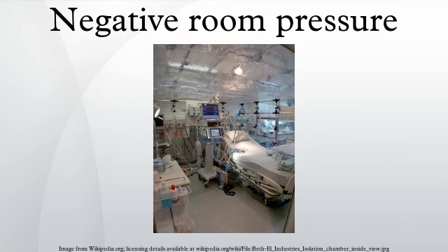Mechanism: negative pressure is generated and maintained by a ventilation system that removes more exhaust air from the room than air is allowed into the room. Air is allowed into the room through a gap under the door. Except for this gap, the room should be as airtight as possible, allowing no air in through cracks and gaps, such as those around windows, light fixtures and electrical outlets. Leakage from these sources can compromise or eliminate room negative pressure.